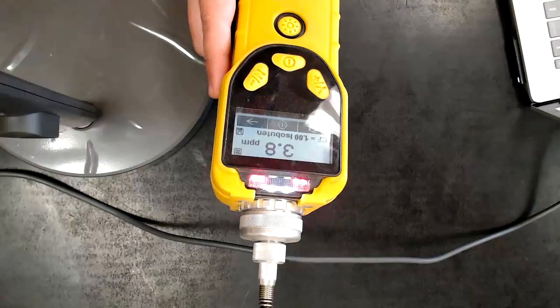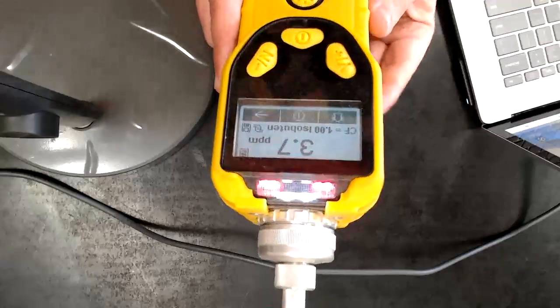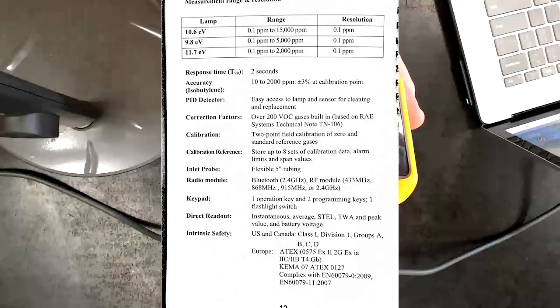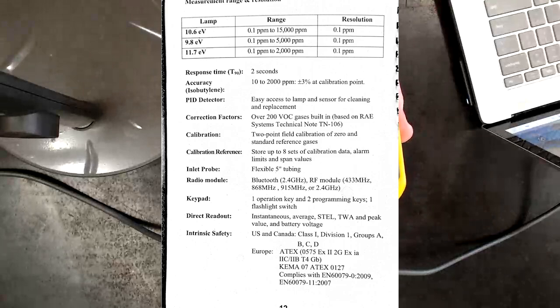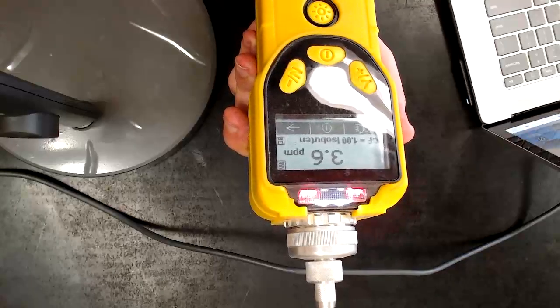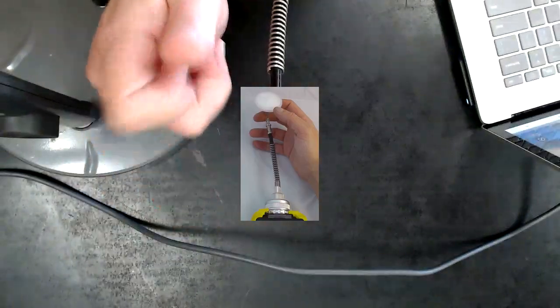Let's take a look at this instrument. The MiniRAE is really good for VOCs, with a wide range. Remember, this is good for 0 to 15,000 ppm for VOCs. The first thing you want to make sure of is that the hydrophobic filter is good. This is a brand new tube.